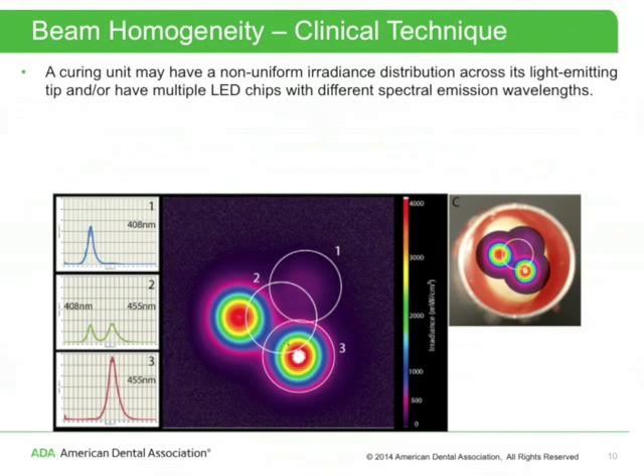A curing unit may have a non-uniform irradiance distribution across its light-emitting tip and/or have multiple LED chips with different spectral emission wavelengths. This close-up of the two-dimensional irradiance distribution image at 2 mm from the light-emitting tip shows circles 1, 2, and 3 corresponding to the approximate position of the 3.9 mm irradiance probe when spectral emission curves were generated. Circle 3 represents the curing unit positioned with the high irradiance region over the probe, showing a single peak at 455 nanometers from a blue LED. Circle 1 corresponds to positioning where the 455 nanometer peak mostly disappears, while the 408 nanometer peak from a violet LED becomes larger.